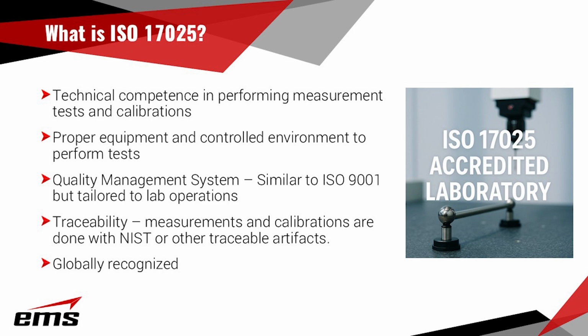All right, so what is ISO 17025? If you see a manufacturer of 3D scanning equipment and it says ISO 17025 accredited lab, that means that they have the technical competence in performing measurement tests and calibrations. So if you're going to send your equipment back to a manufacturer to get recalibrated, typically on an annual basis, or if it has to go in for repairs, you want to know if they are an accredited lab to be able to do that. And that means they have the proper equipment, they have controlled environments, lots of different things to perform their tests.